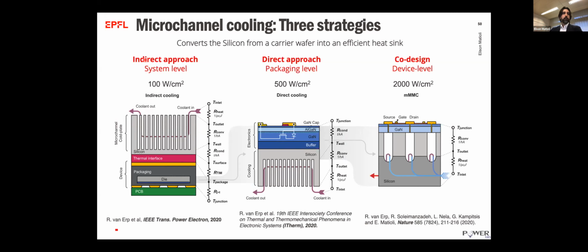The first level is the indirect approach: we make a piece of silicon as a cold plate, attach it with thermal interface material to a packaged device, then flow liquid through it. This can cool down heat fluxes of 100 watts per centimeter square.